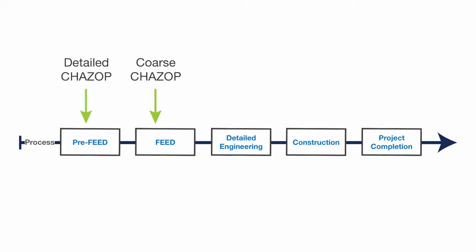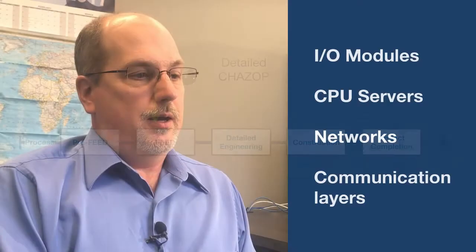A detailed design happens later, looking at every element. We look at I/O modules, CPUs, servers, networks, and different layers of communication as well, to try and determine individual failures and what they look like, what to do about them, and how to safeguard against them.